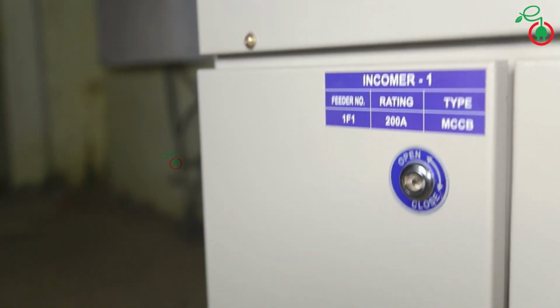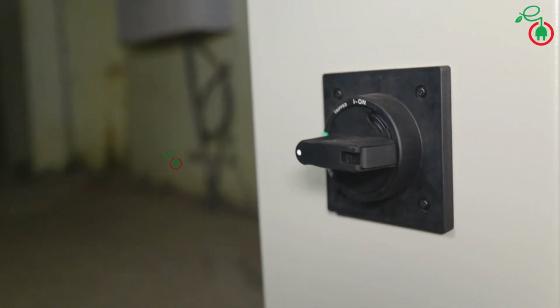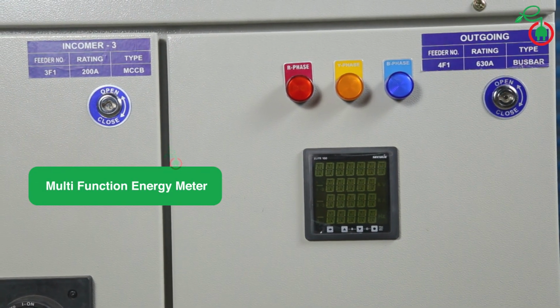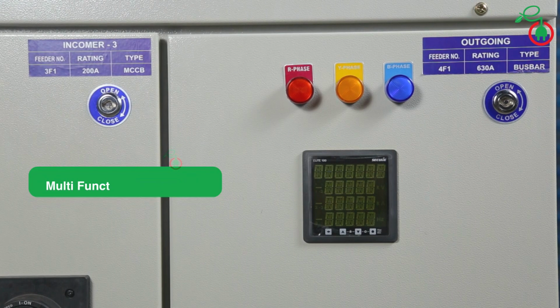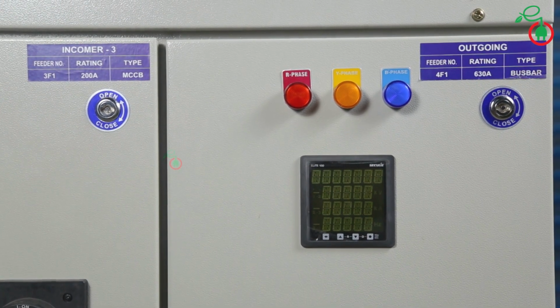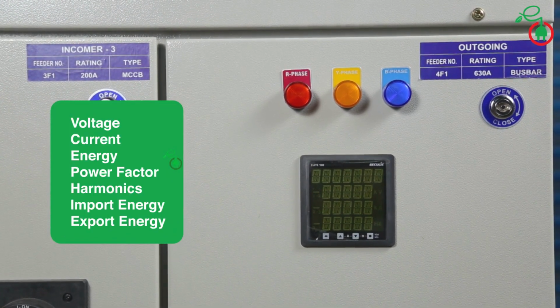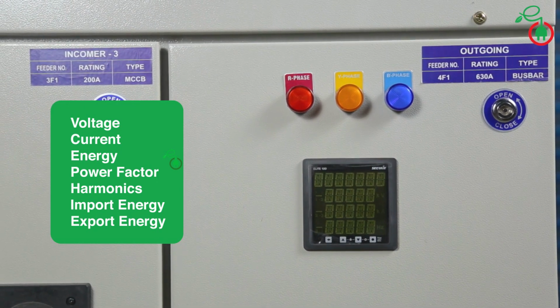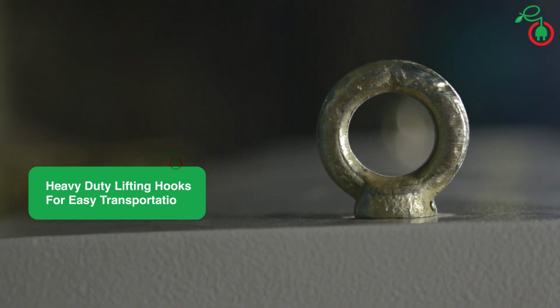In case of any problem, we can see the individual inverter by switching off the particular breaker. The output power is measured with a multifunction meter. The multifunction meter displays the data such as voltage, current, energy, power factor, harmonics, import energy, export energy, and so on. The panel has heavy-duty lifting hooks for easy transportation.